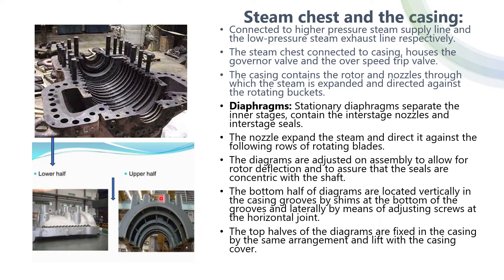The diaphragms are adjusted on the assembly to allow for the rotor deflection and to ensure that the seals are concentric with the shaft. The bottom half of the diaphragms are located vertically in the casing groove by shims at the bottom of the grooves and laterally by means of adjusting a screw at the horizontal joint. The top half of the diaphragms are fixed in the casing by the same arrangement and lift along with the casing cover.